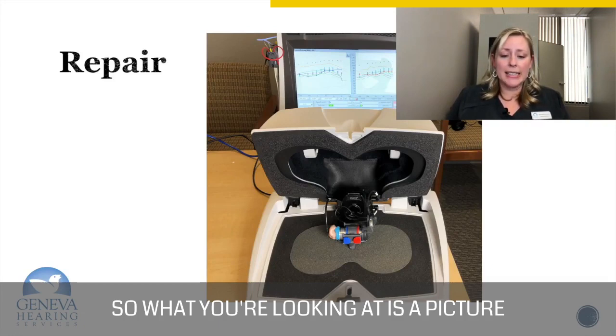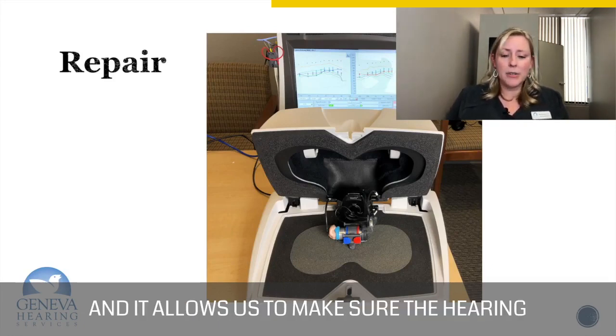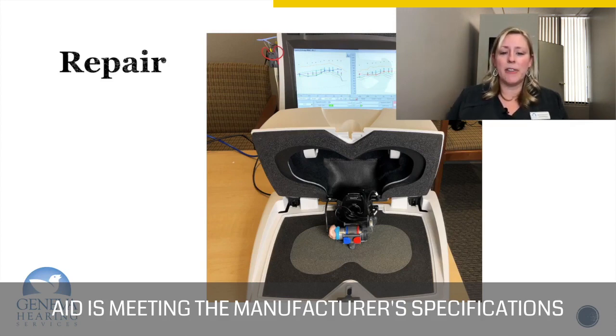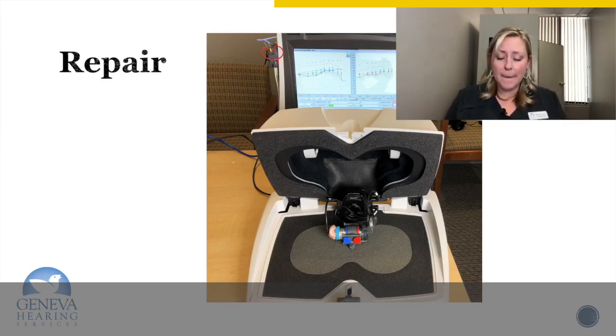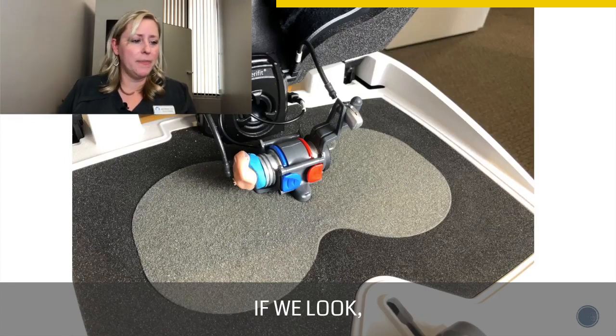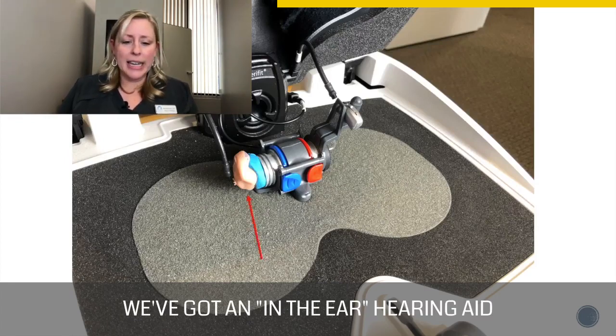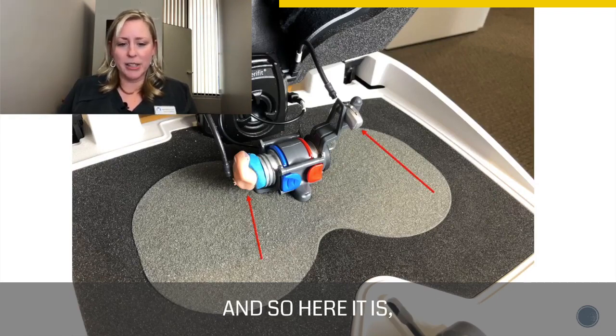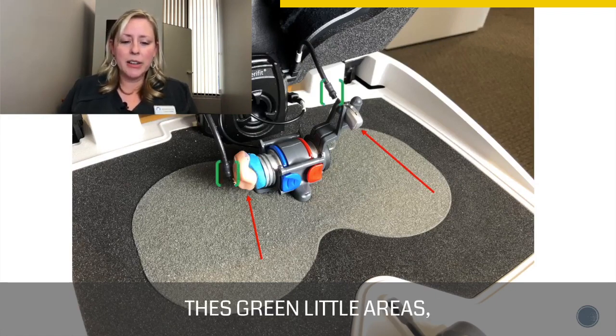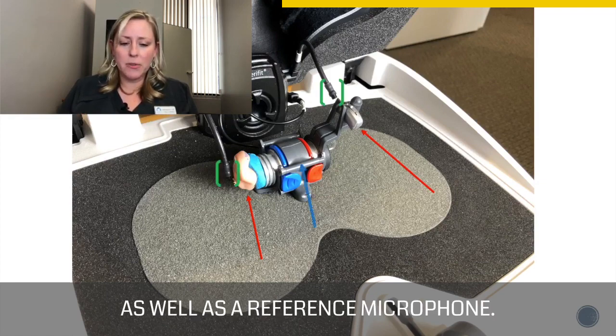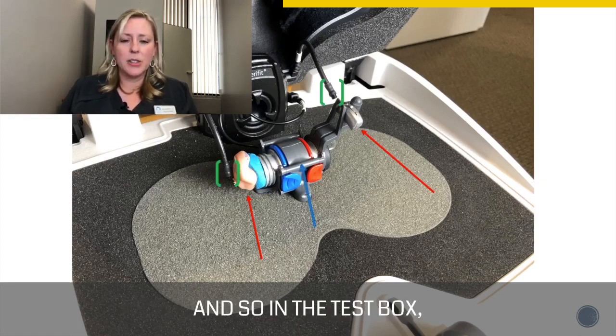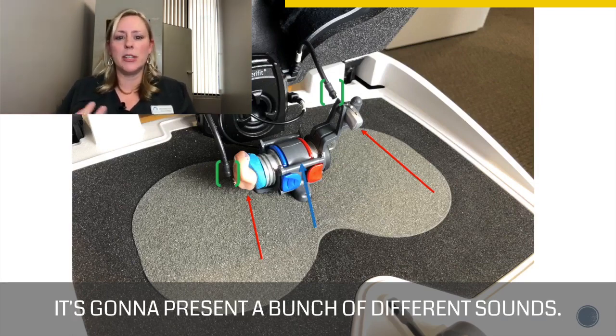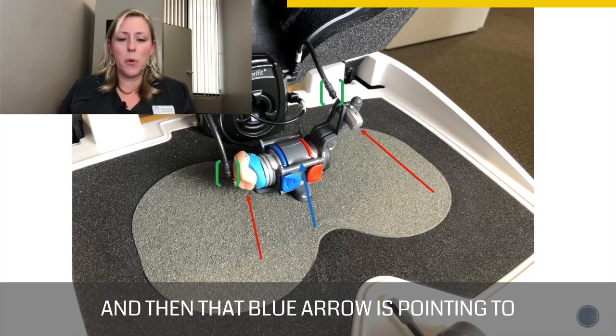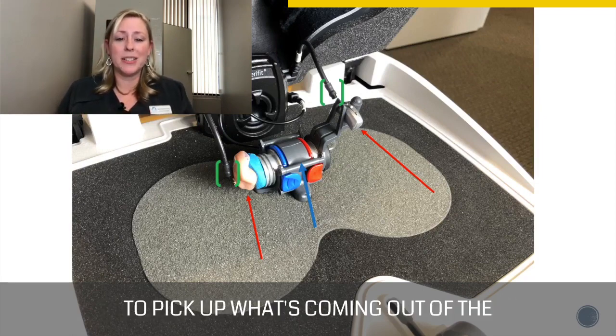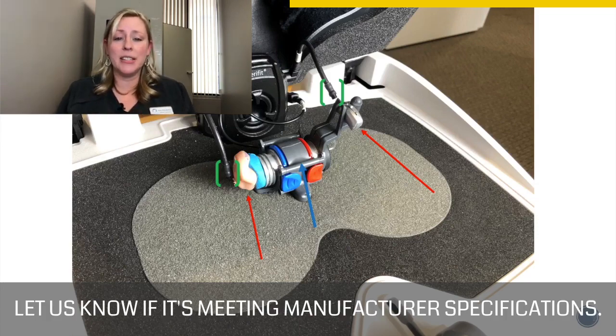So what you're looking at is a picture of our test box, and it allows us to make sure the hearing aid is meeting the manufacturer specifications to make sure it's working properly. So here's just a zoomed in picture. If we look, we've got an in the ear hearing aid and a behind the ear hearing aid. And so here it is in the test box. These green little areas are microphones as well as a reference microphone. And so in the test box, it's going to present a bunch of different sounds. And then that blue arrow is pointing to the reference microphone that's going to pick up what's coming out of the hearing aid and graph it to let us know if it's meeting manufacturer specifications.